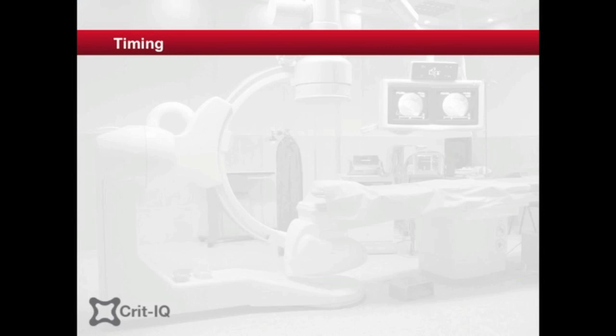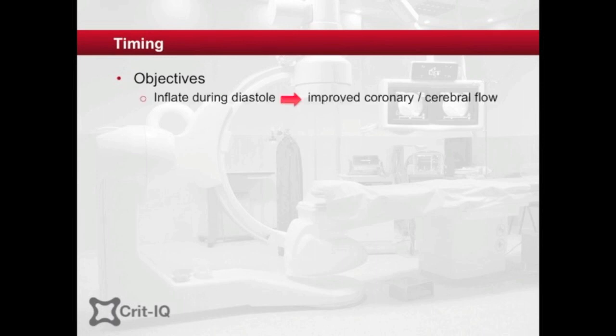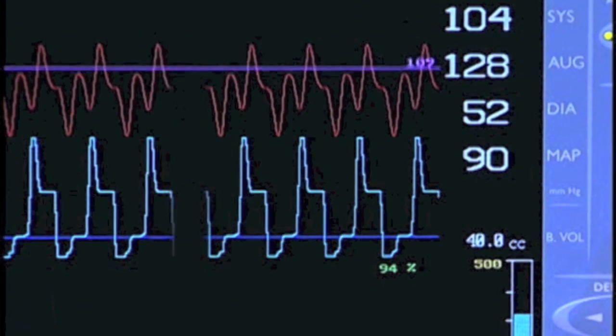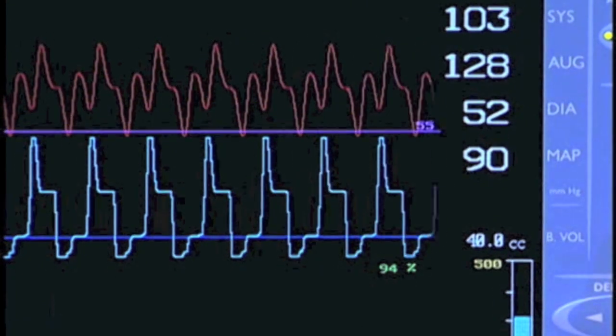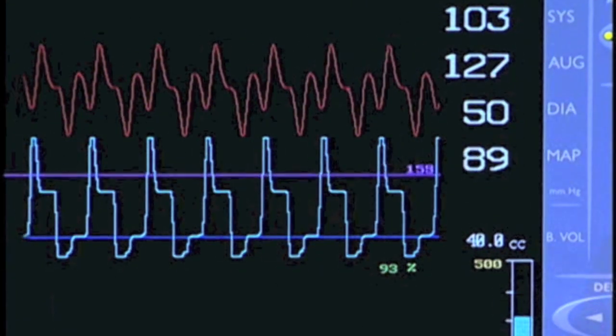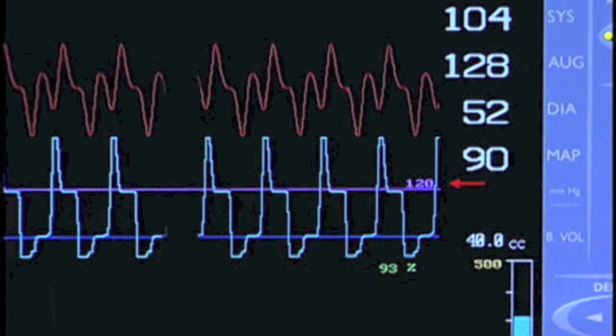Timing. The objective of the intra-aortic balloon pump is to inflate the balloon during diastole, improving diastolic flow of blood in the coronary and cerebral arteries, and to deflate immediately before systole, reducing the afterload against which the weakened heart is contracting. The waveforms taken from the aortic root arterial pressure can be used to determine the appropriateness of the timing of inflation and deflation.